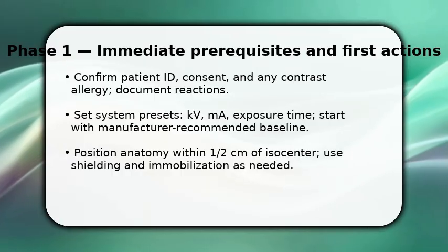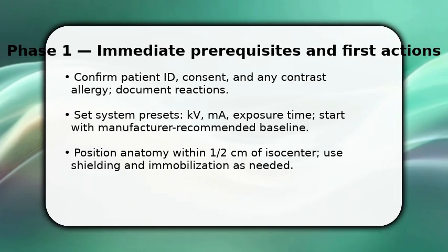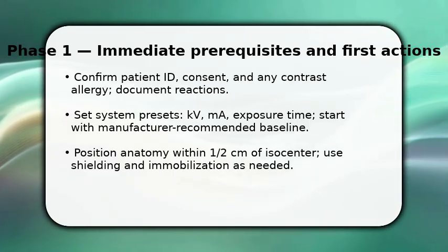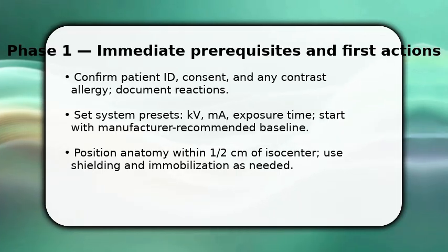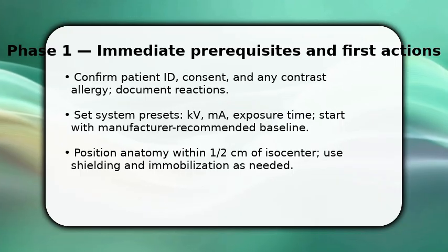You begin by verifying ID and consent and checking contrast allergy. Do this every time. Next, load the machine preset that matches the protocol. Adjust kV and mA from the baseline to suit body habitus.